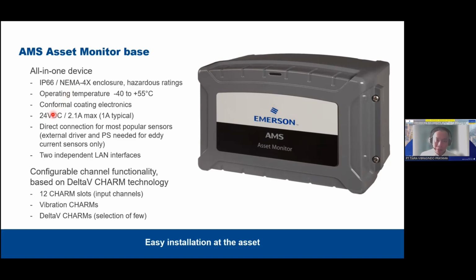It's powered up by a 24-volt DC, right? You have a LAN switch here. So there is an embedded switch inside. So basically, you can daisy chain many asset monitors together, and then one connection back to your control room or to your office for you to open up the browser, right? So that is some of the key points here.